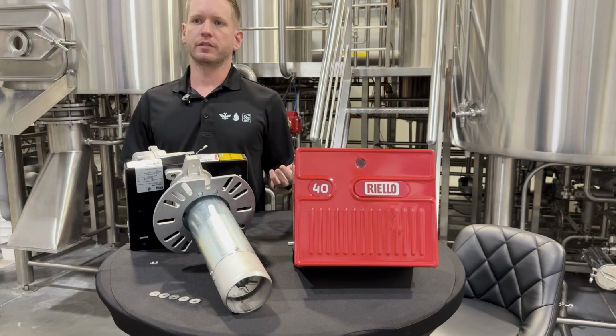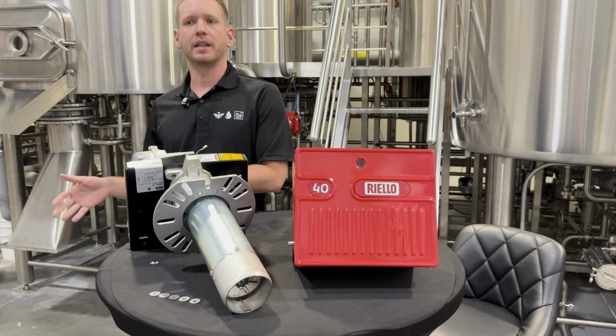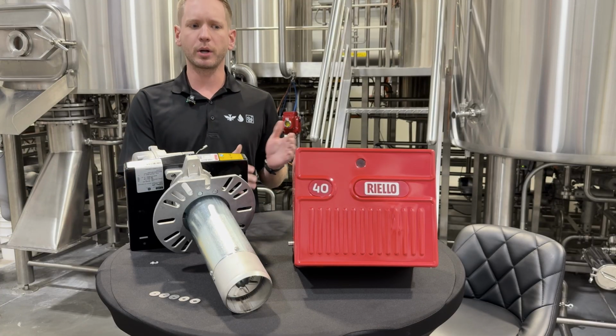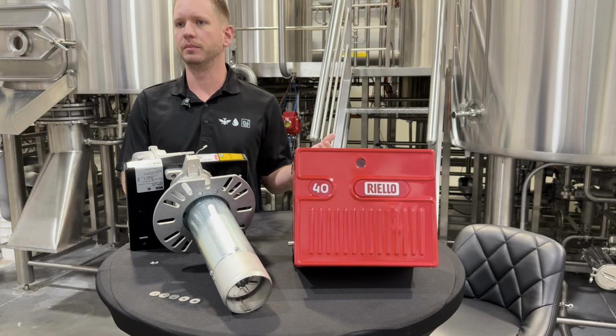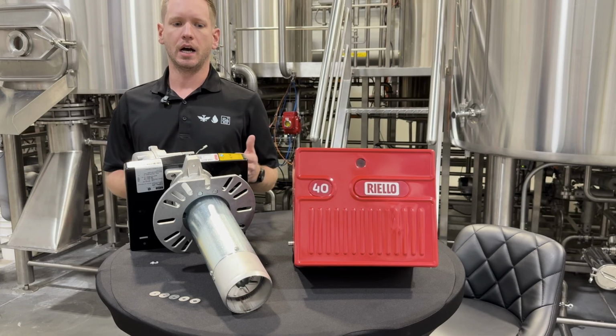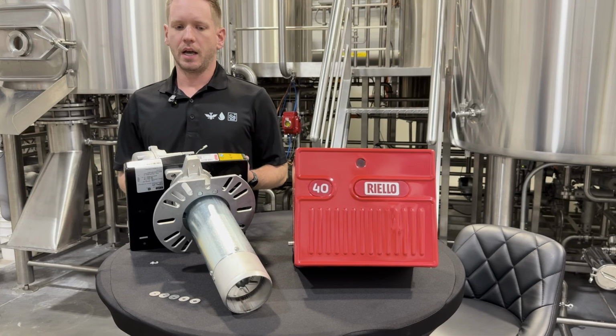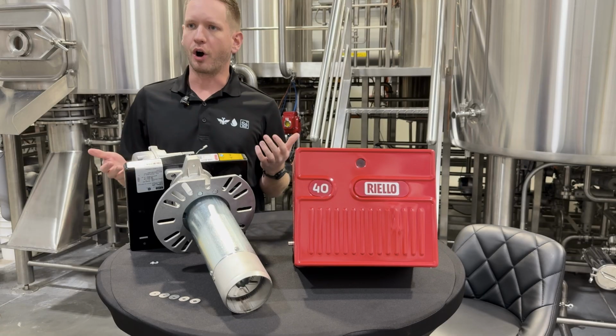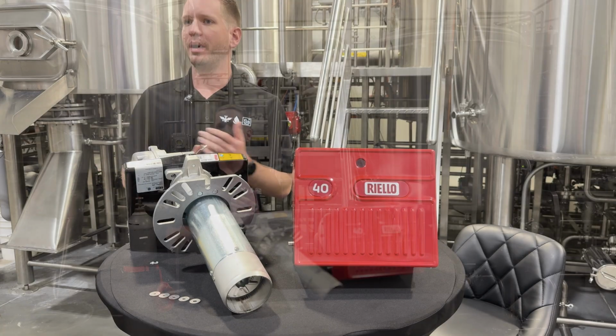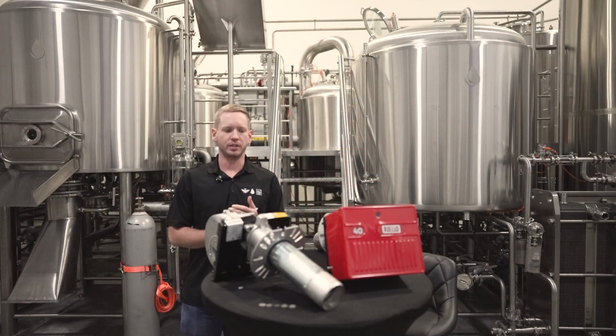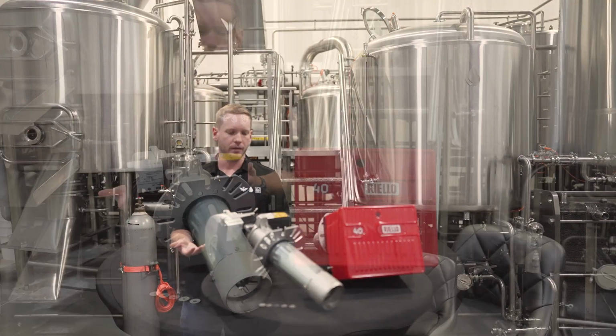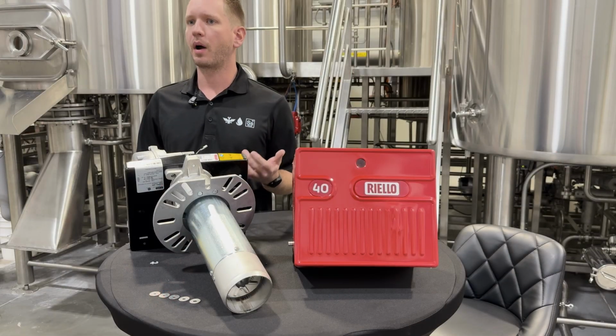So our preferred supplier is Riello. Their burners range from 120,000 to 750,000 BTUs, typically from like a 3.5 barrel system to a 10 to 15 is what we typically do on a brew house. These burners, like most burners, are pretty hardy machines. If well maintained and well taken care of, they should last you an incredibly long time. However, we do see a lot of issues come up when people aren't maintaining these. So a couple things to walk through for proper maintenance.